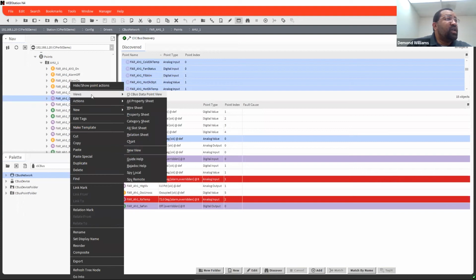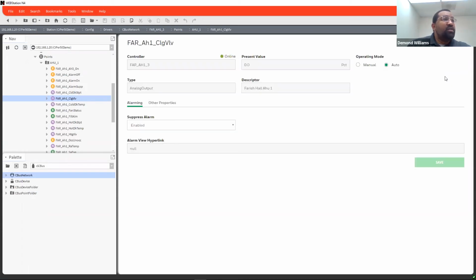on the data point and then go to, they have two different views. You have the C-Bus data point view, which does do initial polling for that point as well. Once it has pulled it in, then this loading time actually is a lot quicker. So this view right here, which is the C-Bus data point view, is basically emulating what you would actually see in the CARE software or their EBI system or their old XBS or XBSI system.